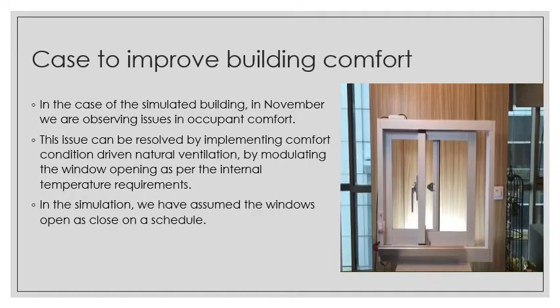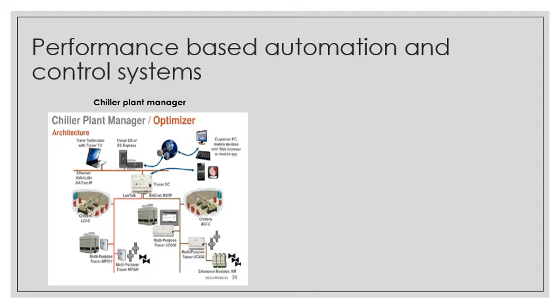Performance-based automation and control systems. For this, we'll discuss 2 cases. First, a chiller plant manager. A chiller plant manager essentially manages the operation of a chiller plant, that is the chiller and the pumps, as per the lowest possible specific energy consumption requirement, kilowatt required of energy per tonnage of cooling delivered. It takes in feedback from the line pressure and temperature sensors to control the speed of the pump and the operation and loading of the chillers.